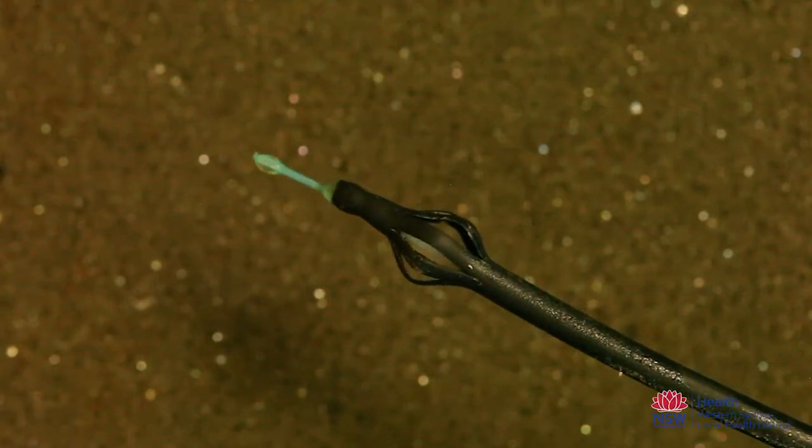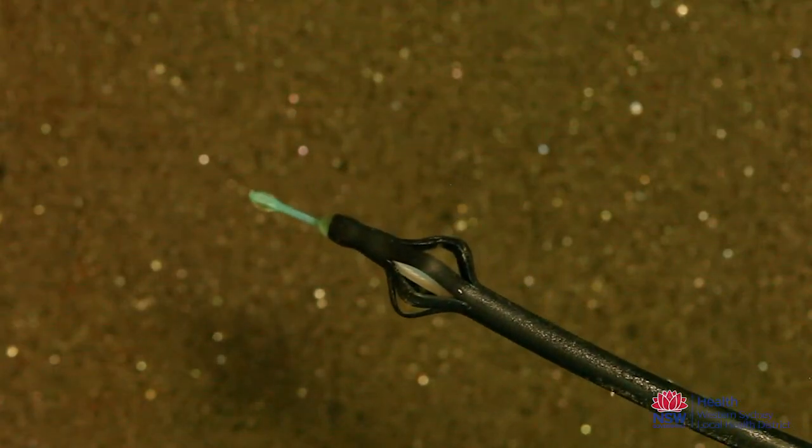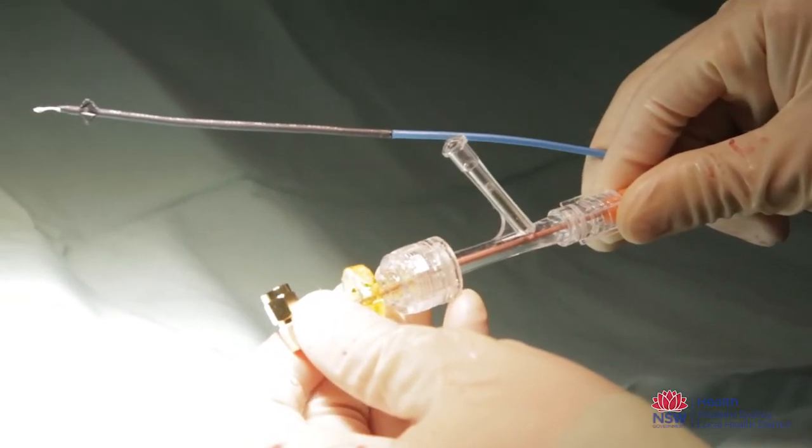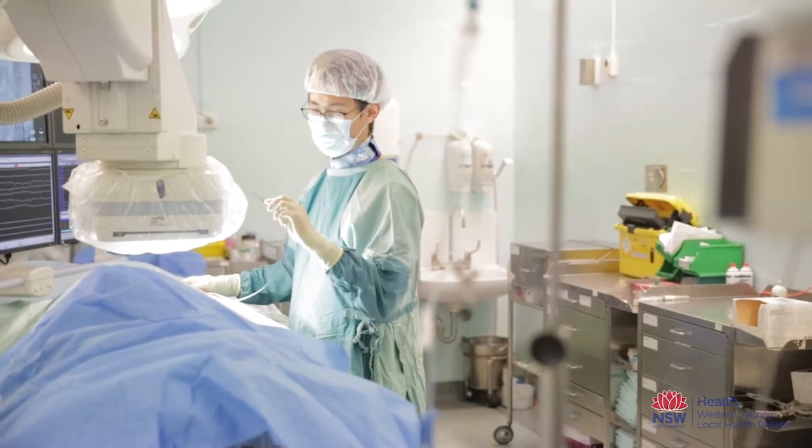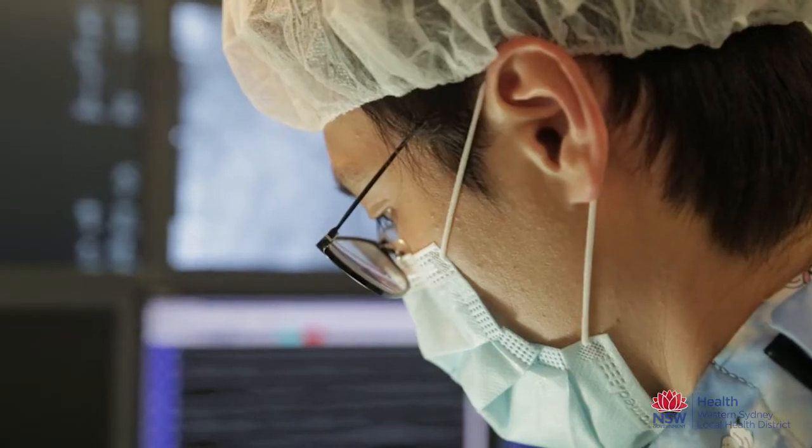We designed and made a prototype microwave emitting catheter that can be used for renal denervation. It works by radiating microwaves and deeply heating tissues around the artery in a 360 degree fashion, while sparing the artery itself, which is kept cool by arterial blood flow.